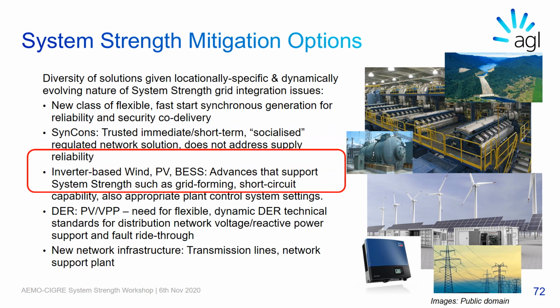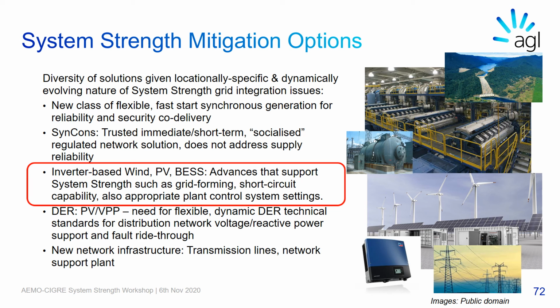As for inverter-based or IBR generation, newer technologies that can provide system strength as well as other dynamic grid voltage and frequency support, such as grid forming, voltage source converter, short circuit current and fault level contribution, will be desirable in order to backfill the retirement of legacy synchronous plant. Also, appropriate plant control system settings that can enable regional network plants to operate in a stable manner, in particular to minimize incidences of inverter control system interaction or SSCI under a reasonably diverse range of system operating conditions, is also another key desirable. This approach, of course, was demonstrated in the recent successful resolution of the Western Murray constraint, which also affected, among others, inverter generation plant such as AGL's Broken Hill Solar Farm and Silverton Wind Farm.